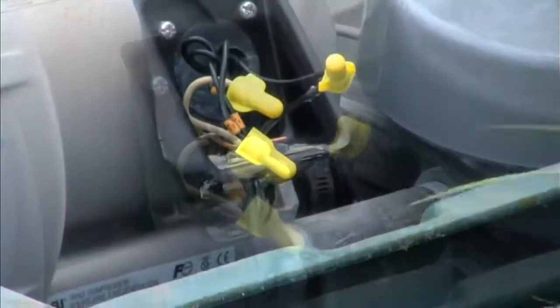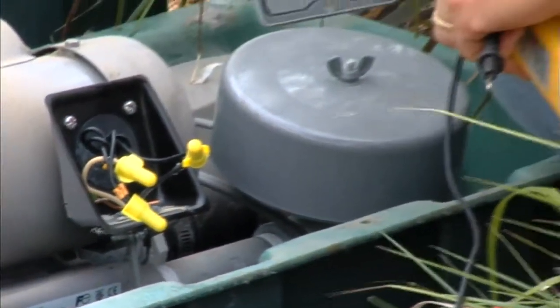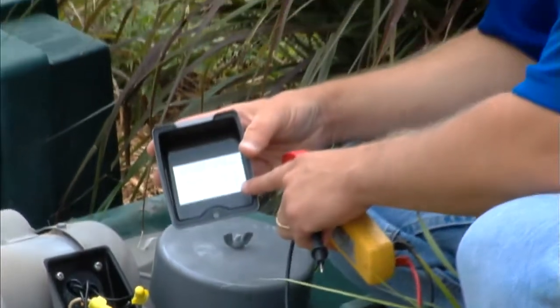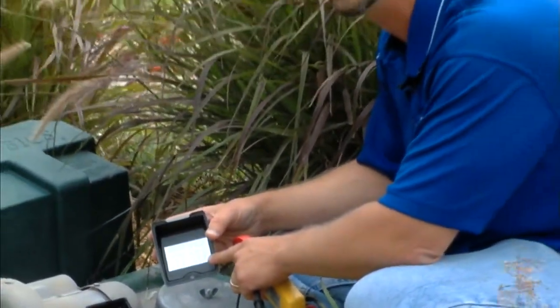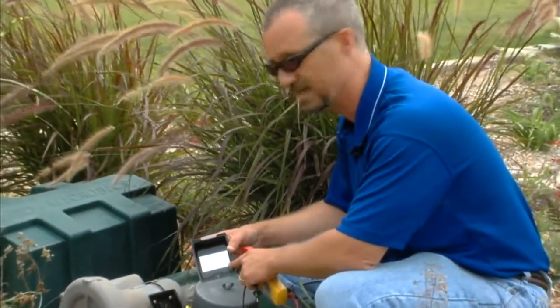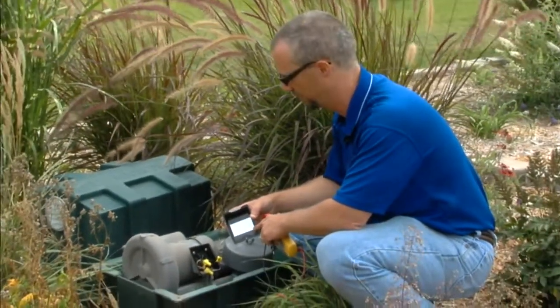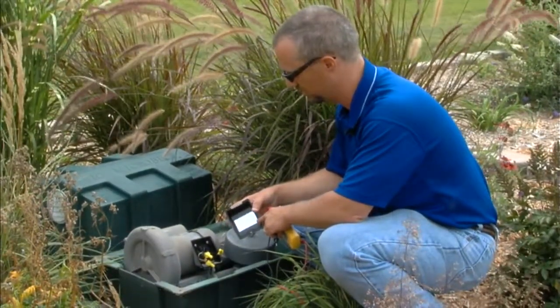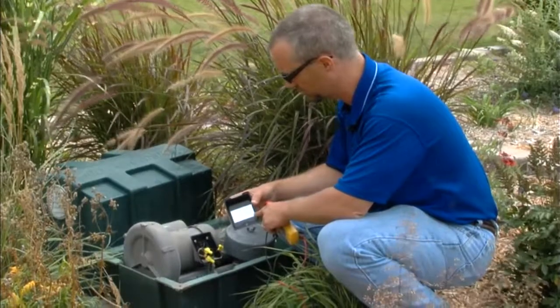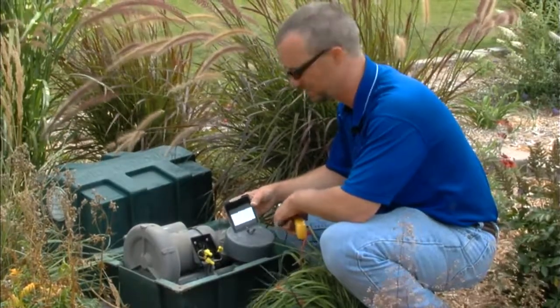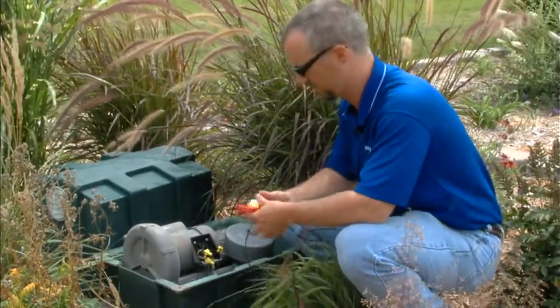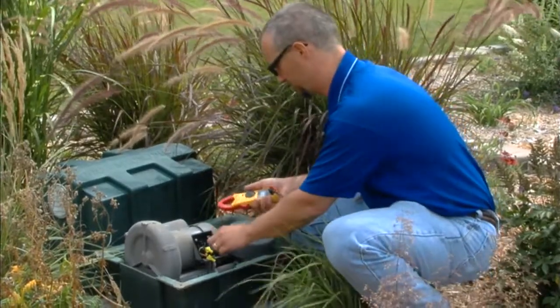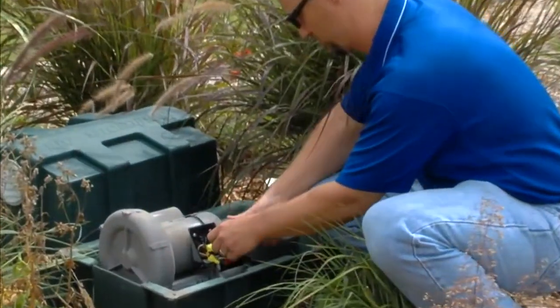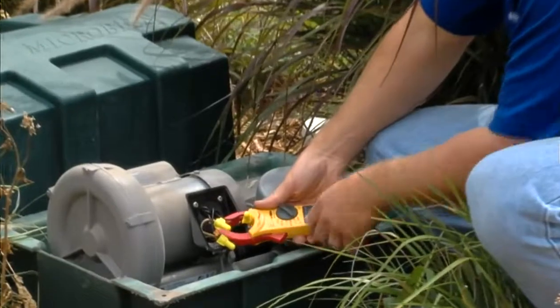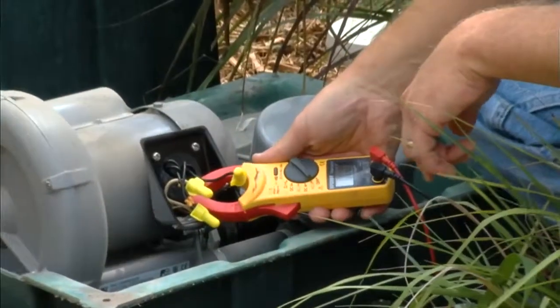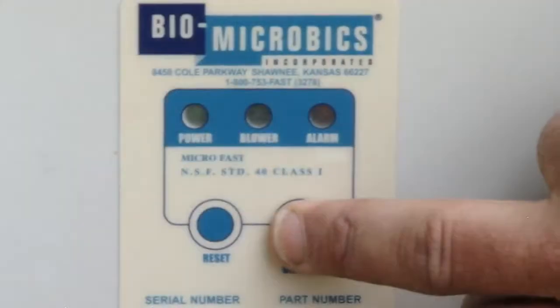leg. And if you're unfamiliar with whether you have high voltage or low voltage, 110 being low and 220 being high, you can look at the schematic on the back cover of the blower's electrical panel or electrical junction box to determine which wire you need to look at. So next we'll get our amp clamp around our hot leg here, and then we'll have somebody turn the power back on. We'll be able to get an amp reading.